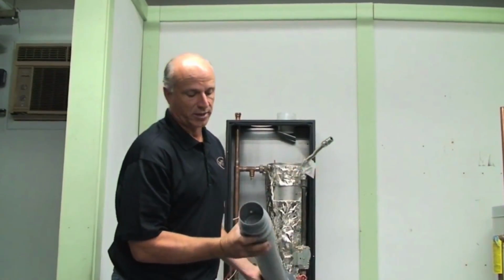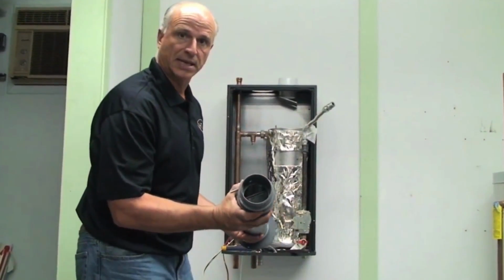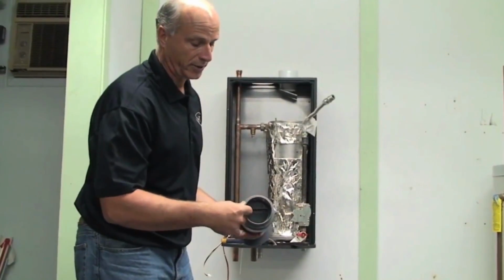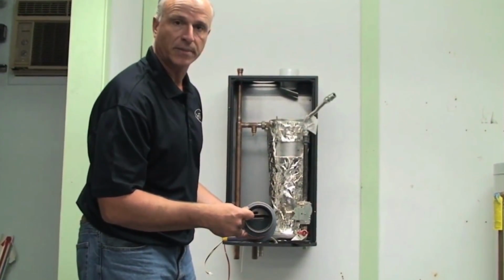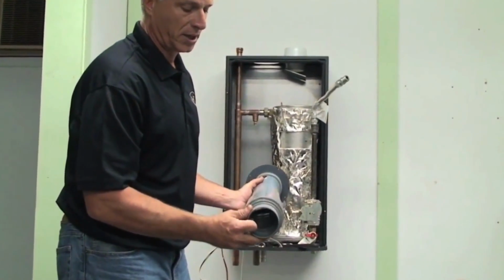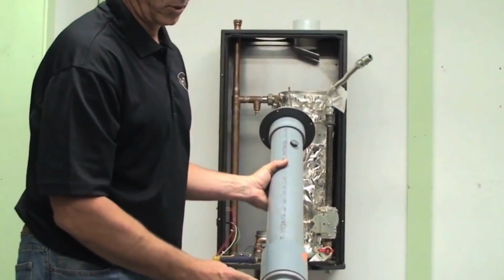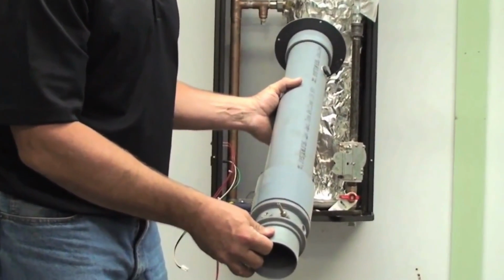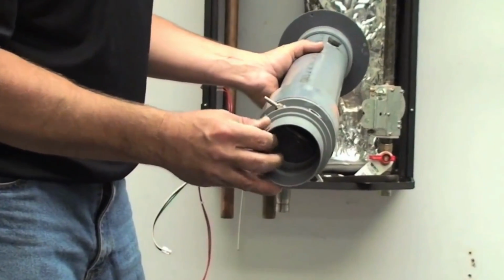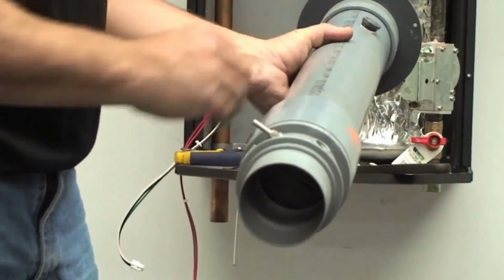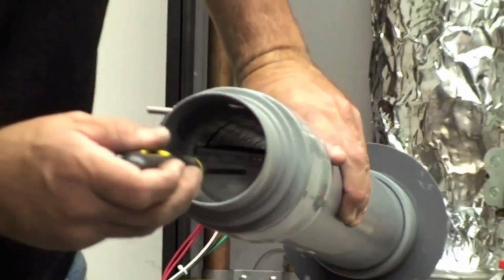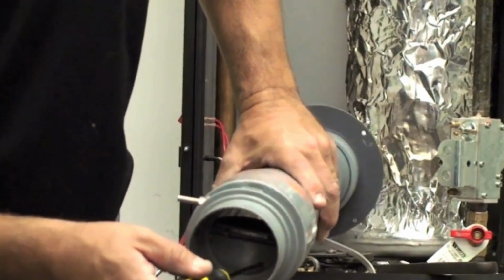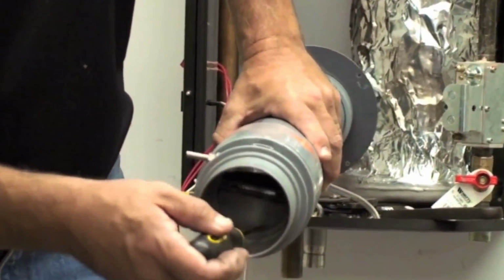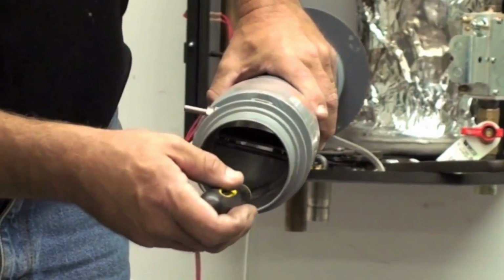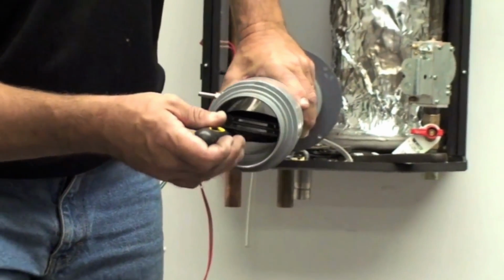Your check system is on the bottom, and you might be able to see that in there. If we can zoom in here, you'll see that there's the flue check system, and then you can see the other tapped holes for our sensors that we have on the outlet of our flue assembly. All this is made out of CPVC. So you can see our check system in the flue, and there's a pivoting point here with 2 flaps, and I'll just move it for you so you can see it.